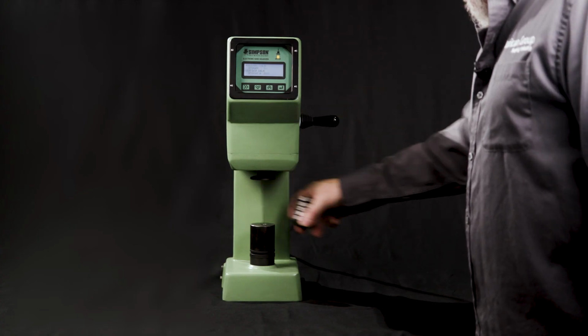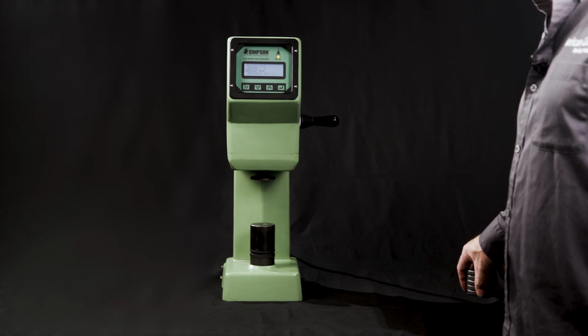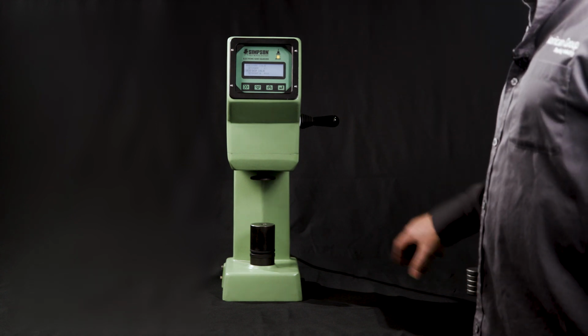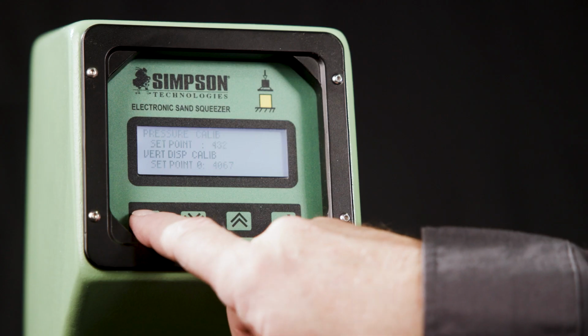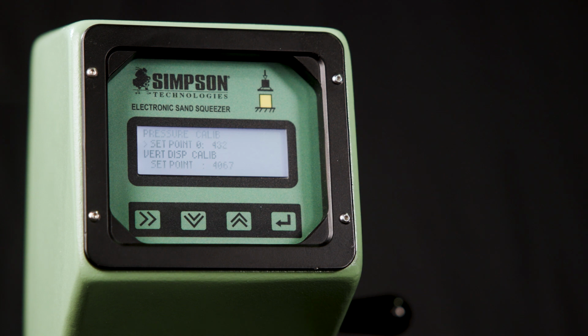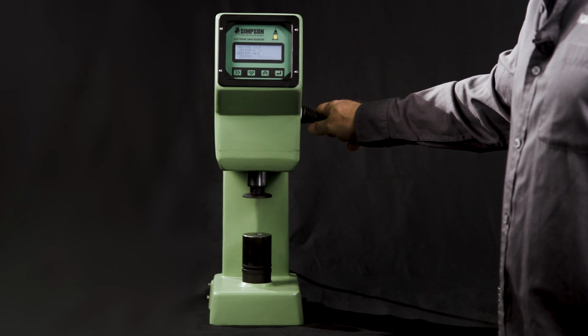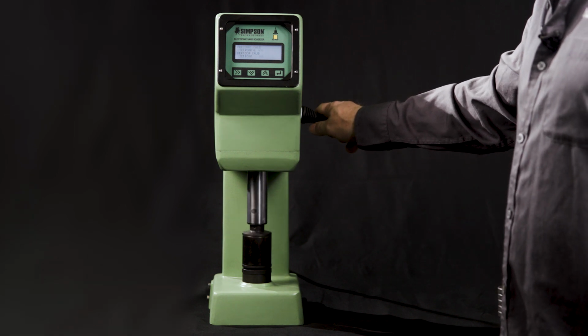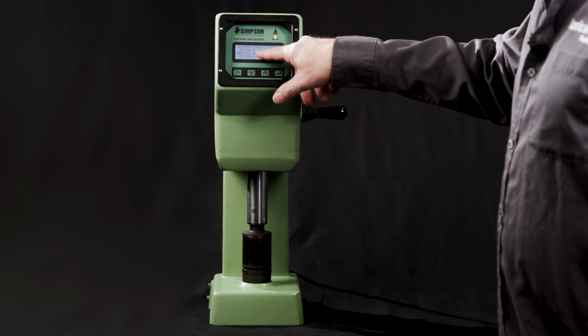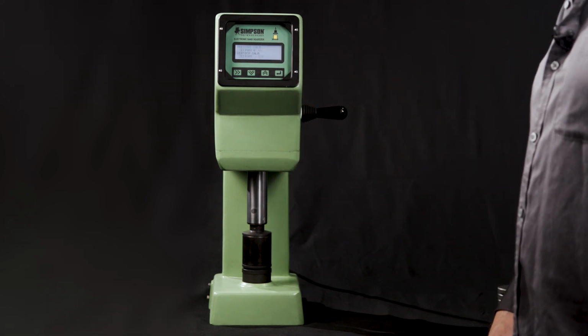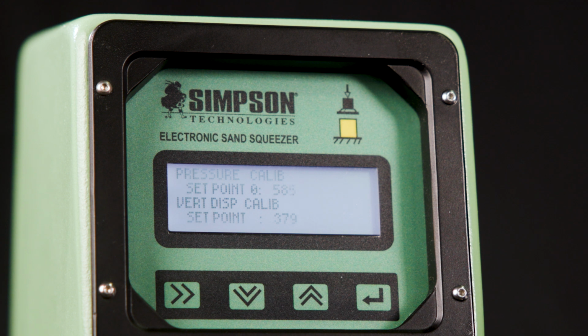Bring the piston up. We're going to take these 5 10mm plugs out, and then we're going to do the pressure calibration. We are going to press the right arrow, which is going to change the cursor from the vertical displacement up to the pressure calibration. And at this point, we need to adjust the pressure for 1 bar. This is going to travel a little bit slower because the pressure has been decreased. We get to this point here. This number right there is going to decrease from the initial indication. Once it stabilizes, we're going to press the up arrow again.